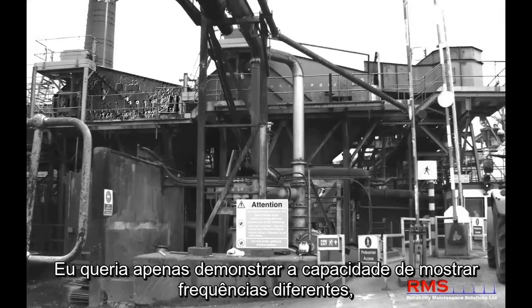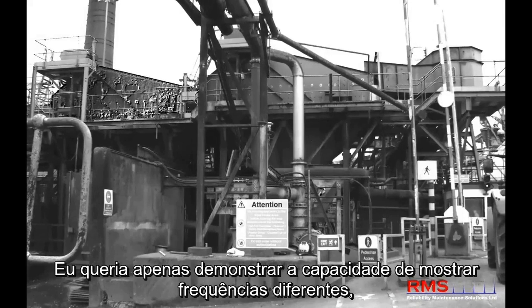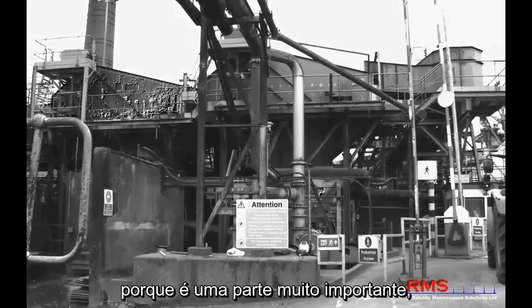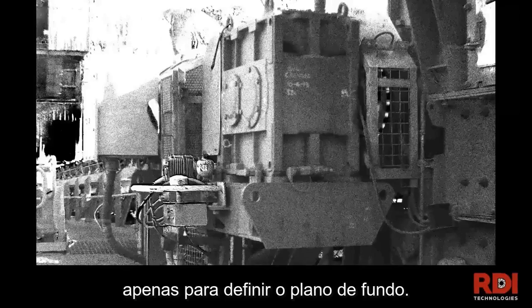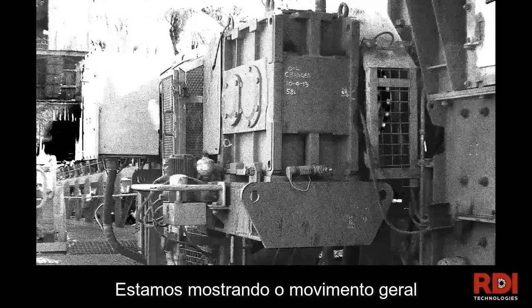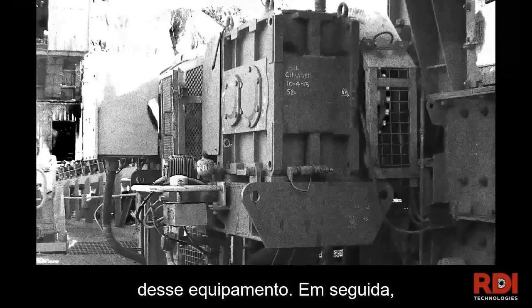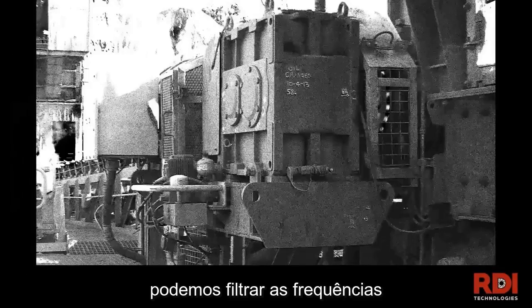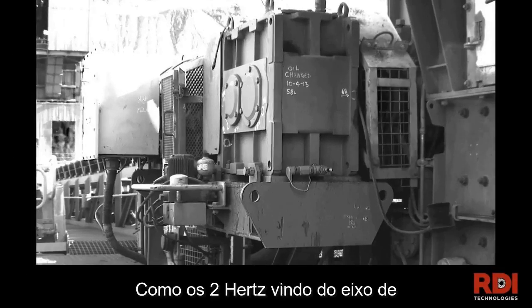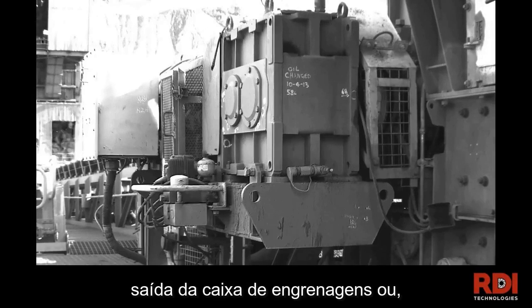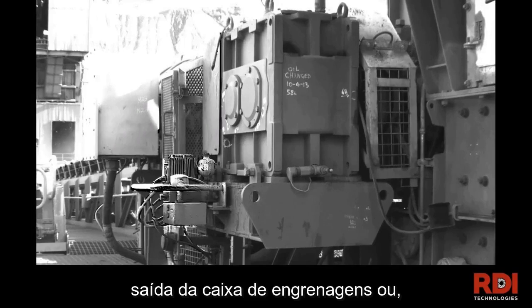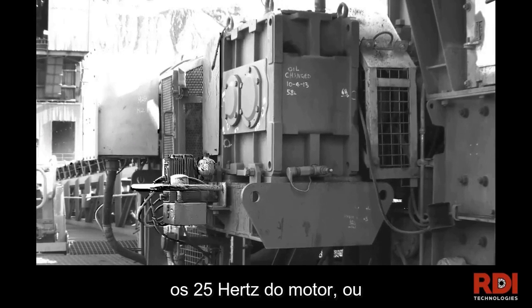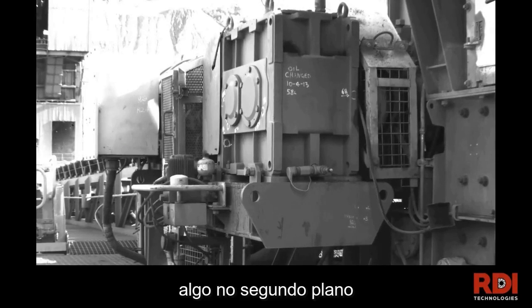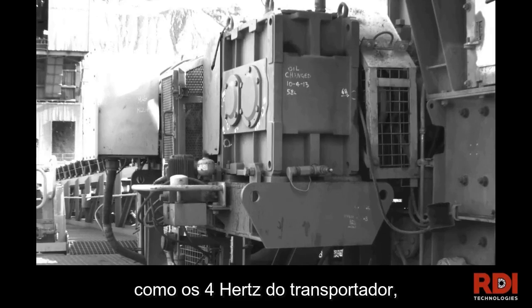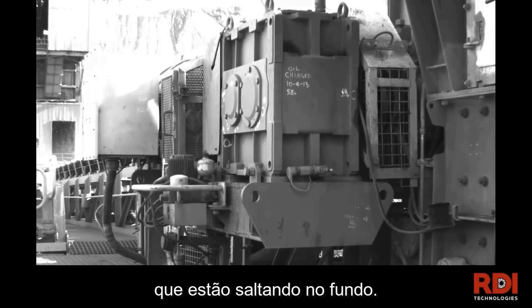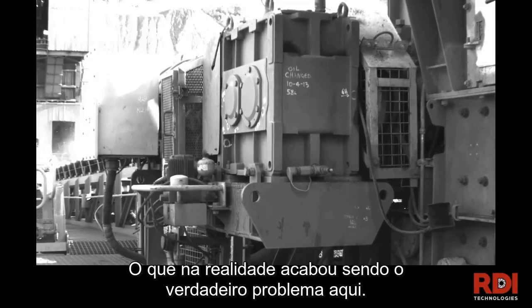So again, what I wanted to do is just demonstrate the ability to show different frequencies, because it's a very important part of this, just to set up the background. Again, we're showing this overall motion of this motor here, and then we can filter for individual frequencies, like the 2 hertz of the band of the output of the gearbox, or say the 25 hertz for the motor, or say something in the background like the 4 hertz on this conveyor that's bouncing in the background, which actually ended up being the real issue here.